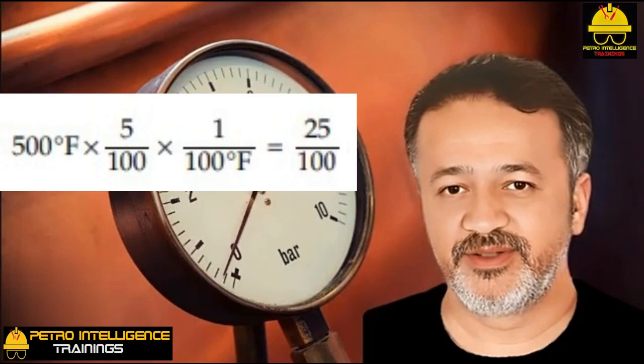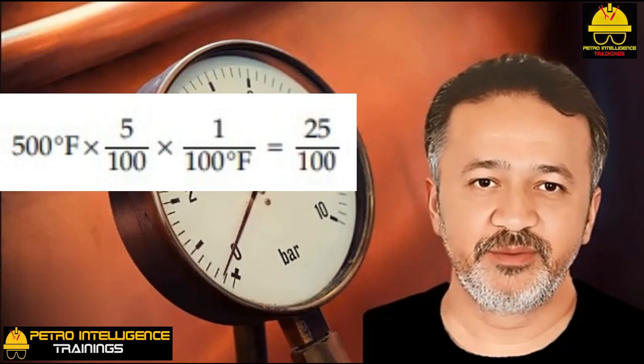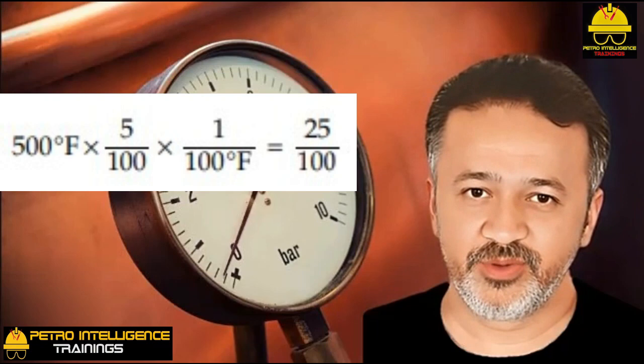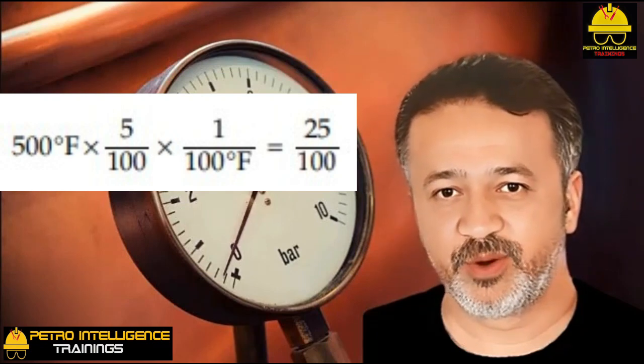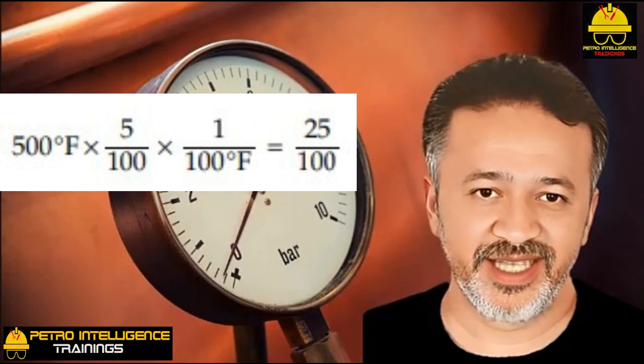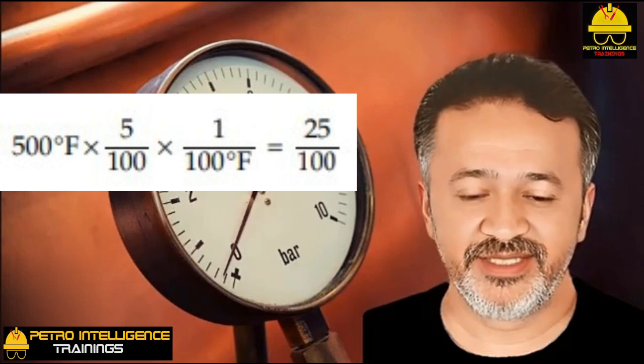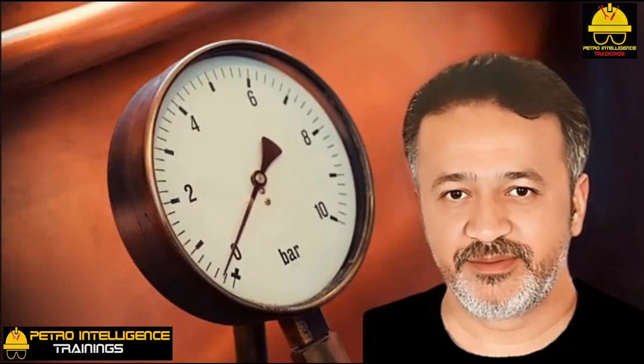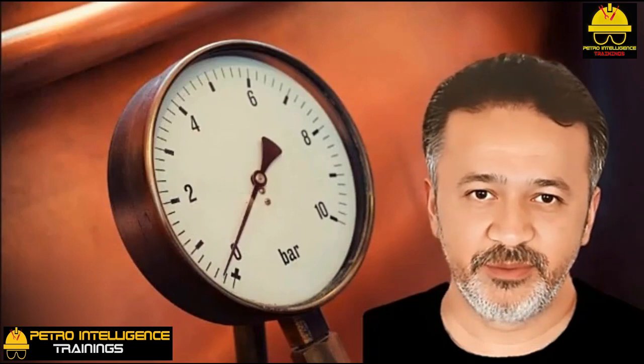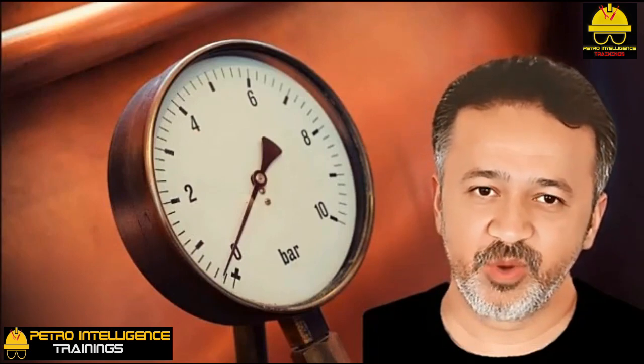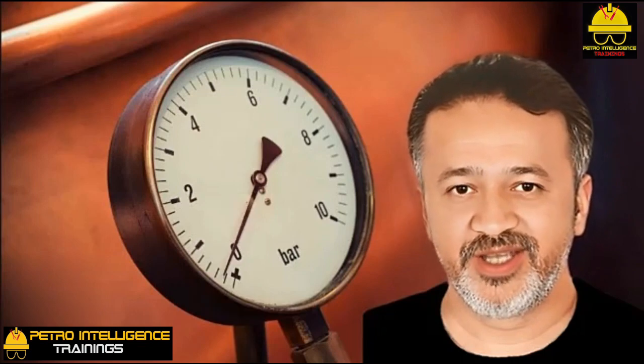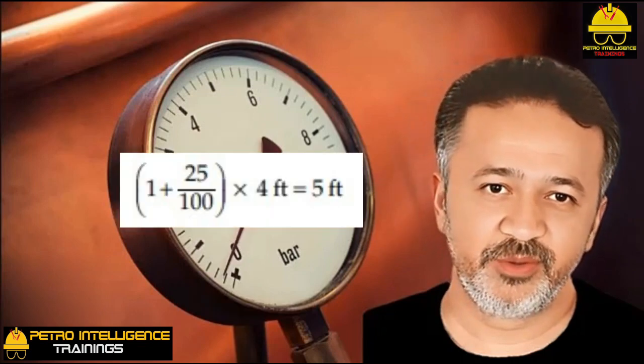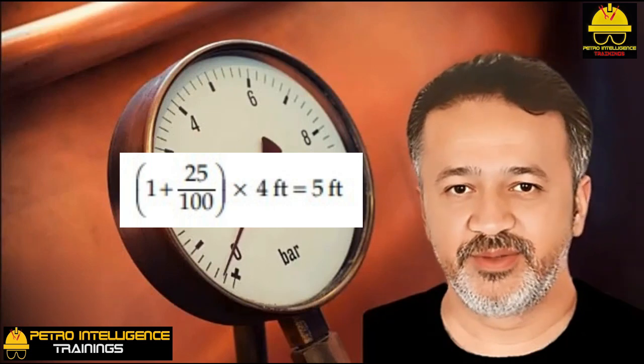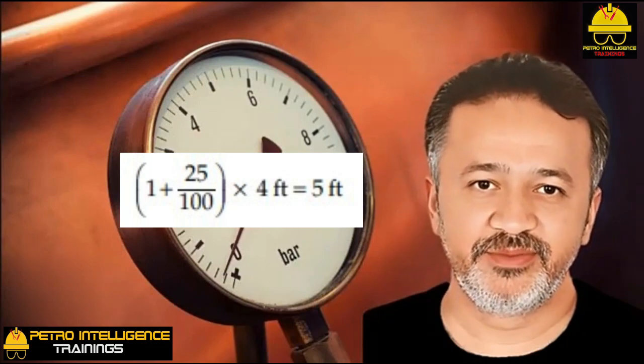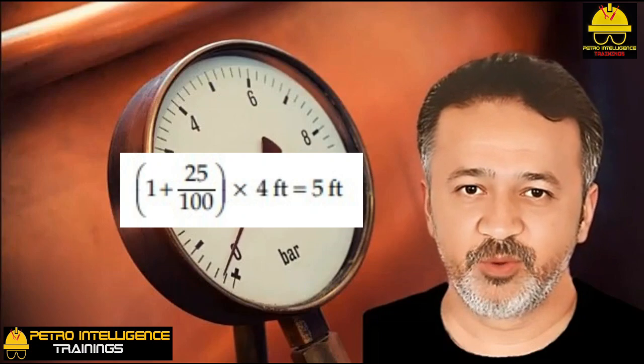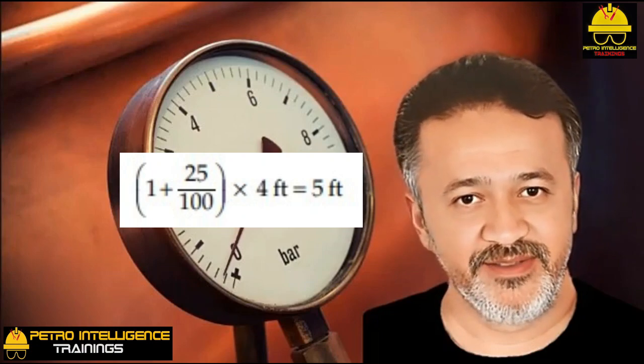Explanation: 500 degrees Fahrenheit times 5 divided by 100 times 1 divided by 100 degree F equals 25 divided by 100. This means that the liquid in the gauge glass is 25% denser than the liquid in the tower bottom. Assuming a linear relationship between density and volume, the level of liquid in the tower above the bottom tap of the gauge glass must be (1 plus 25 divided by 100) times 4 feet equals 5 feet. In other words, the liquid in the tower is 1 foot above the level shown in the glass.